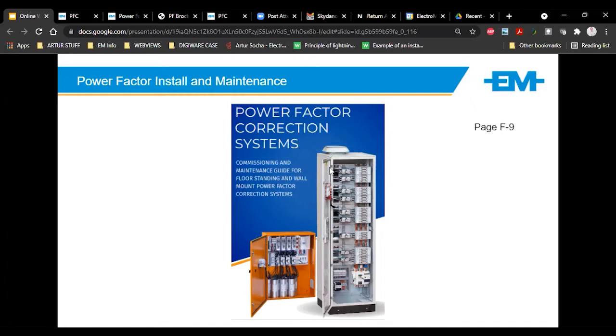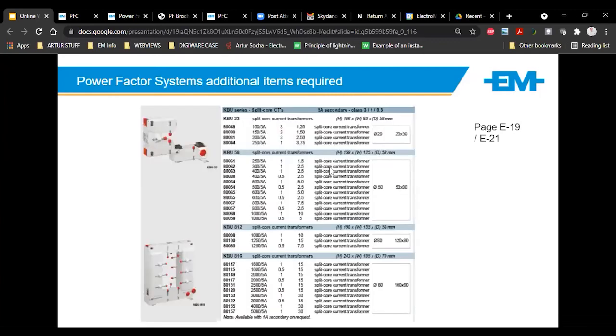So the maintenance guide is to show you how to install a wall and a floor standing system. And then it's got a basic maintenance log: what to measure on the cap, see if the cap has deteriorated, do I need to replace the capacitors? Okay. Another critical component for a power factor system is the CT. The CT is separate because we don't know the size of your breaker or your cables. You have to select the CT accordingly. I like using split core CTs on existing infrastructure. If you've got a 2,500 amp breaker, you don't feel like disconnecting all the bus bar work. You can clip in these split core CTs, which we also sell.